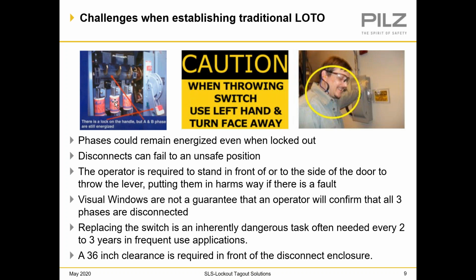So also with that, disconnects can fail to an unsafe position. The operator is required to stand in front of or on the side of the door to throw the lever, putting them in harm's way if there is a fault. And then, as I mentioned, visual windows are available, but that doesn't guarantee that the operator will actually see that all 3 phases have been disconnected, because you have human error in the mix.